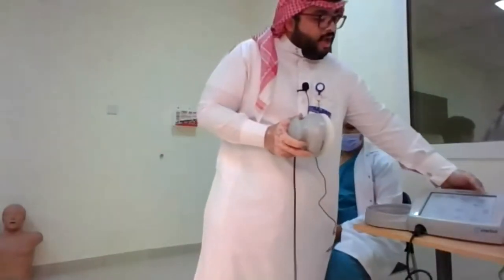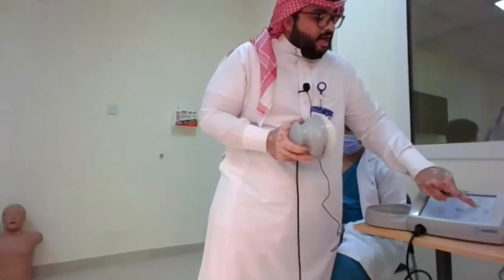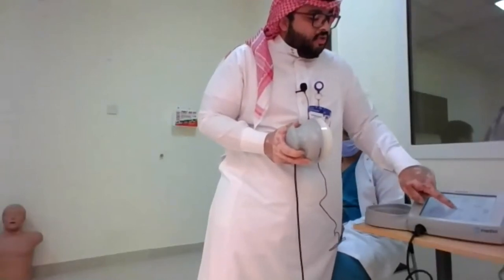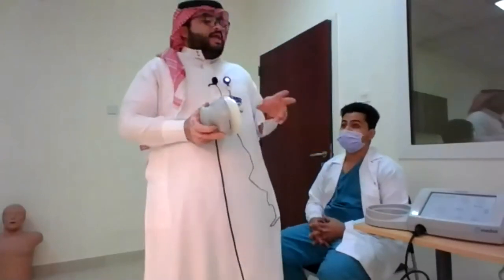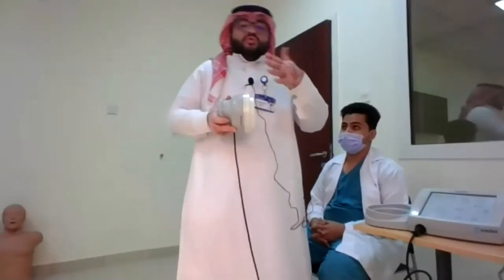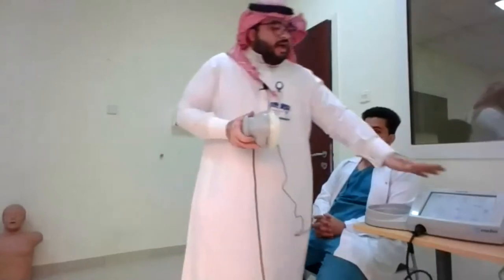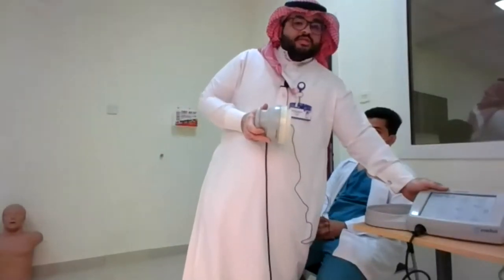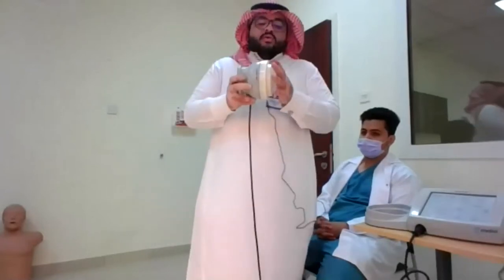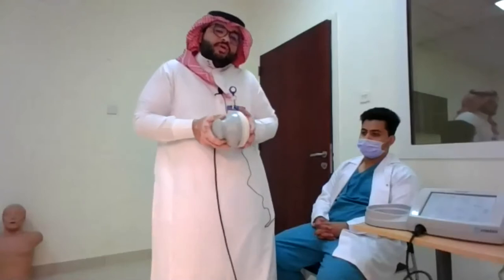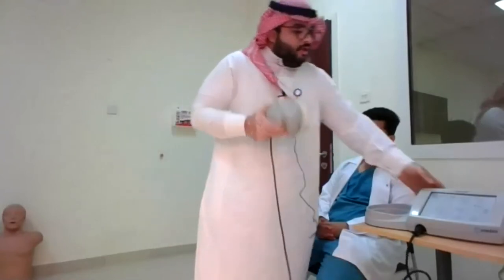I will start the intensity for adults at 90%. Some studies say the tissue starts to vibrate between 40 and 42 hertz, which is why the default setting when we turn the machine on is 40. Then we can change it according to the patient's condition, the intensity of secretion, and so on, because once we increase the hertz, we increase the vibration. So I will start to use it.